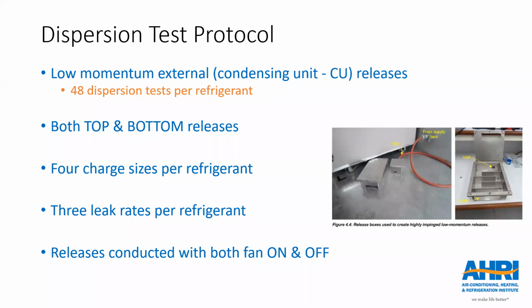These low momentum releases were done at both the top and the bottom of the display case to simulate the presence of a top or bottom mounted condensing unit. They were done at four different charge sizes and three different leak rates, which we discussed previously. And they were done both with the condenser fan on and off so that we could see the impact of using air circulation as a mitigation measure. Next slide, please.